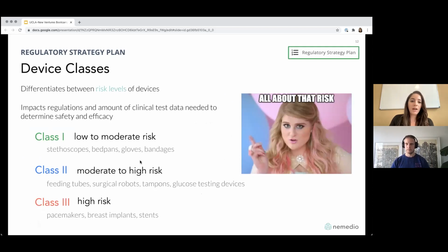So there's this concept of device classes. You may have heard of, like, a class 2 510K. This is probably one of the more common phrases you might hear thrown around. Because the way that FDA thinks about devices is based on risk levels. So class 1 devices are low to moderate risk. Class 2 devices are, again, the biggest category. They're moderate to high risk devices. And these encompass a super wide range of things. Surgical robots are often included in class 2. Feeding tubes, tampons, testing devices, things like that are often in class 2.